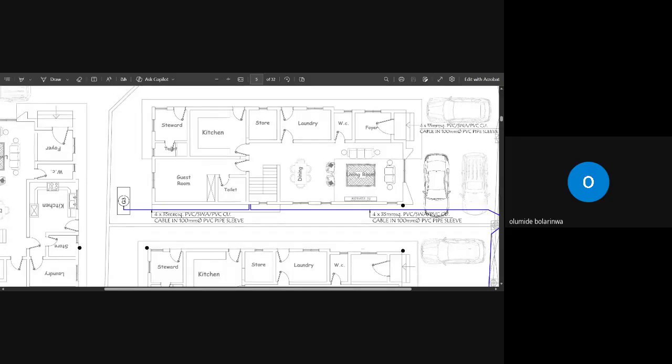It is fine. So what was the total, please? 63.67. Now to that 63.67 you allow for slack, which is 10%. That 10% is 6.3. So roughly it is around 70 meters. Are you there? Yes, sir. Do you get my explanation?